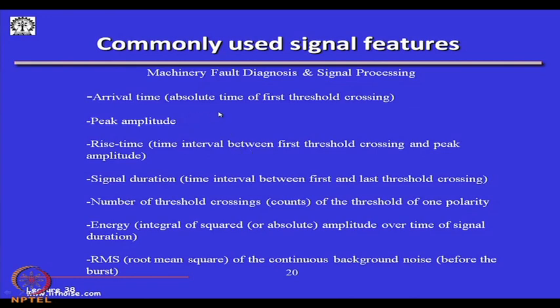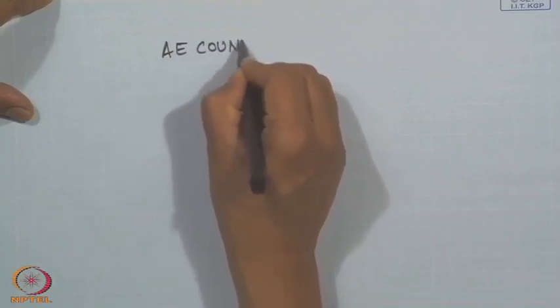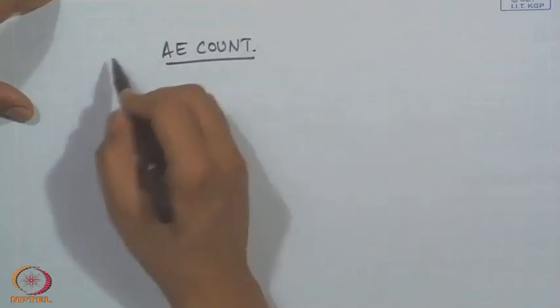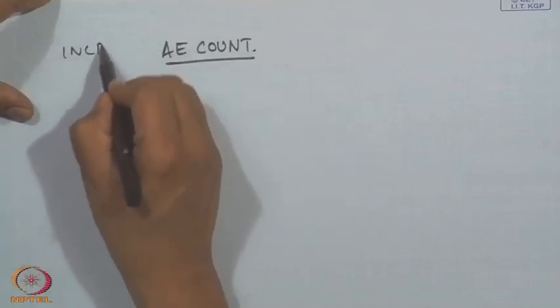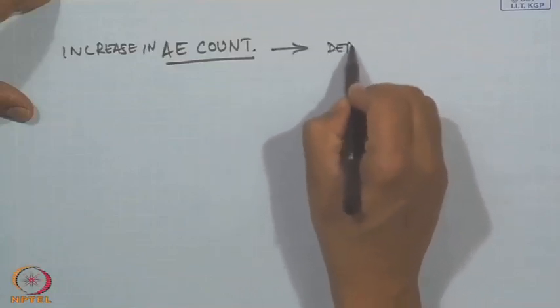Arrival time is the absolute time of the first threshold crossing; peak amplitude is the maximum; rise time is the interval between the first threshold and peak amplitude; signal duration is the time interval between first and last threshold crossing; number of threshold crossings are the AE counts. AE counts were earlier used as a method of detecting whether an acoustic event has happened, and an increase in AE count represents a defect in the structure.